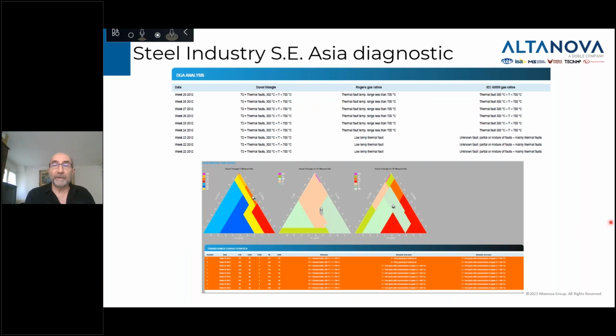And then you put it in the different diagnostic tools. So what we've done is we put them in the Duval triangle, the Rogers gas ratio, and the IEC 60599 gas ratio. And as I said earlier, when you look at those 3 different diagnostic tools, depending on the measurement time, mostly all of them come to the same conclusion, that you have some kind of a thermal fault between 300 and 700 degrees.